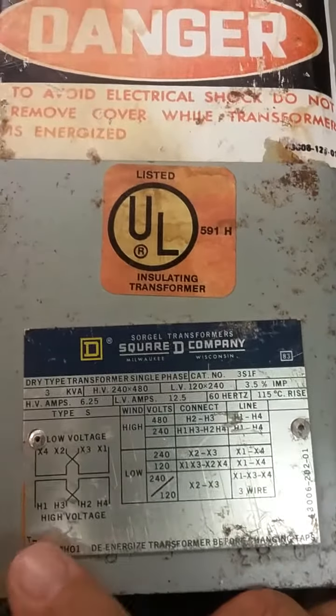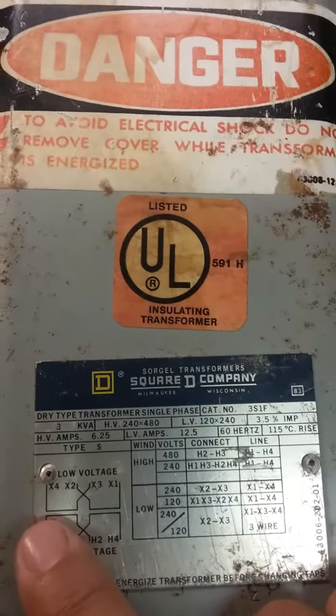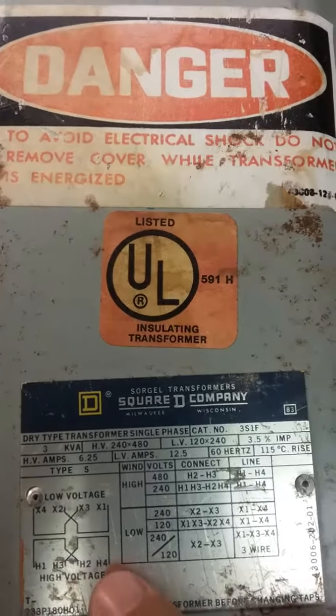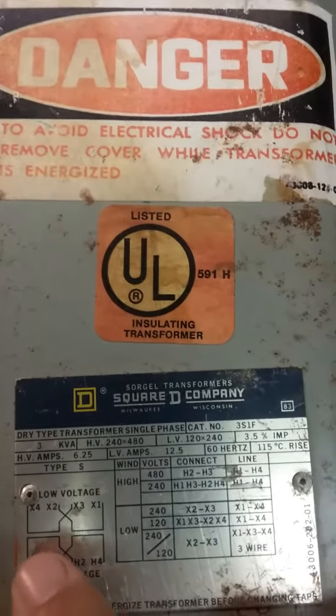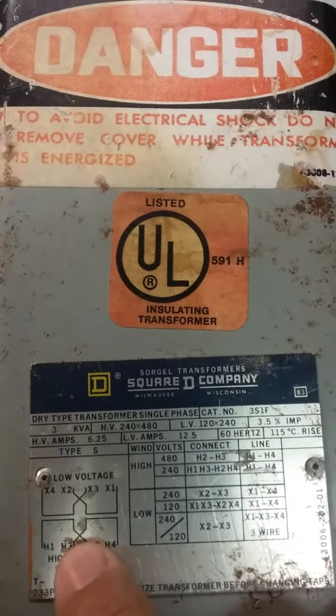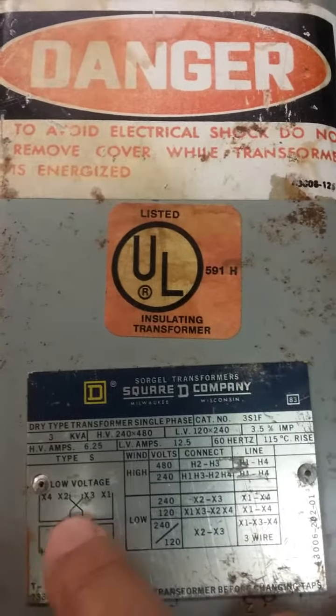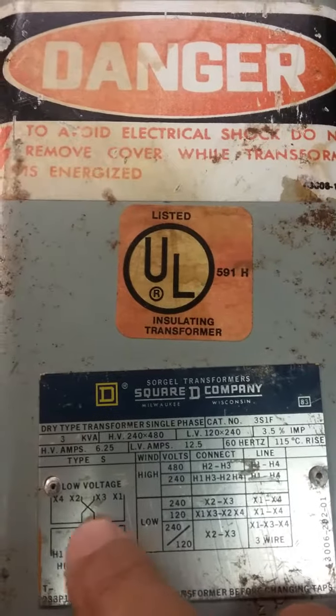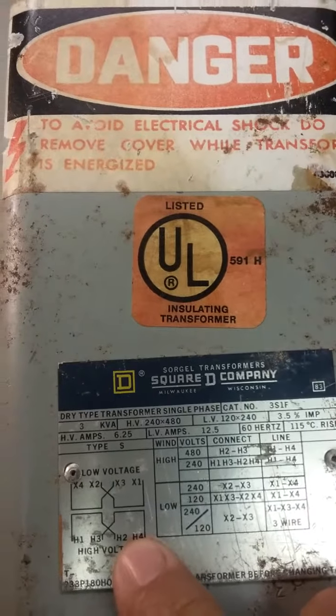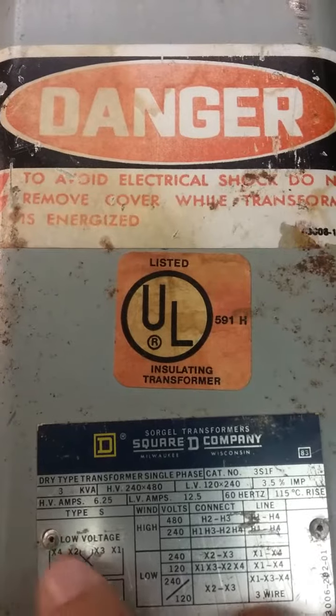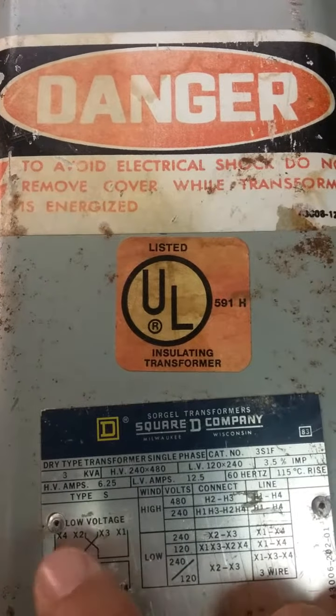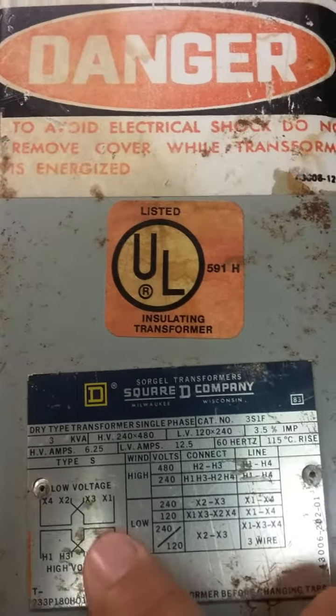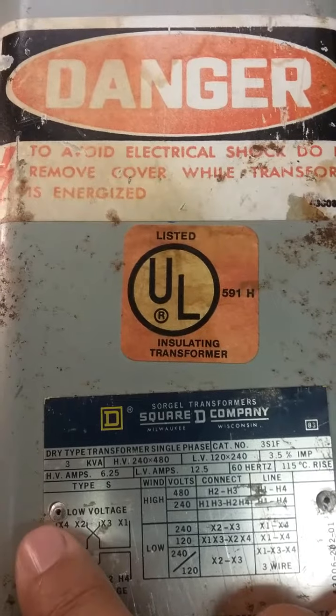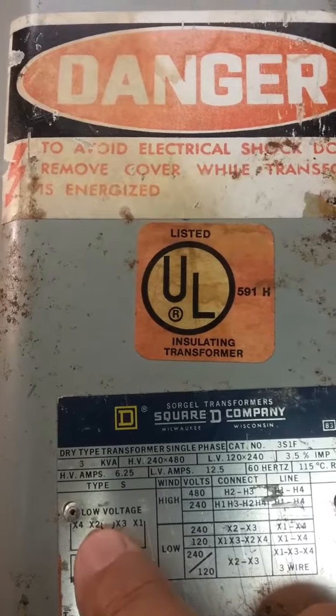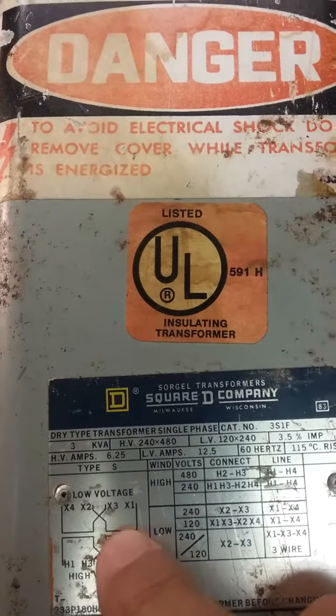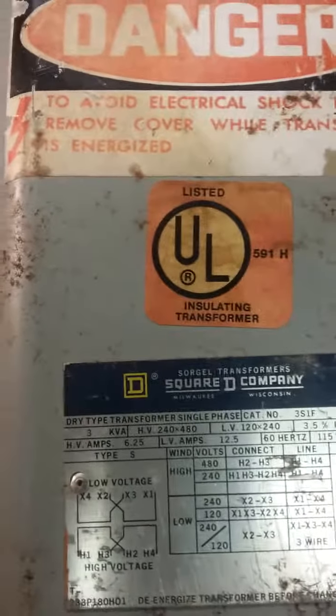And the way this works is, on the high voltage side, you can run 240 across H1 and H4, and actually you can run 240 or 480. And just tie H3 and H2 together, which makes one equivalent series. The two are in series, so it creates one equivalent coil on the primary. And then on the output, you can pull off the full. If you put 480 in, you can get 240 out across the entire X1 to X4 if you tie X2 and X3 together, which again makes a comparable single coil output on the secondary.